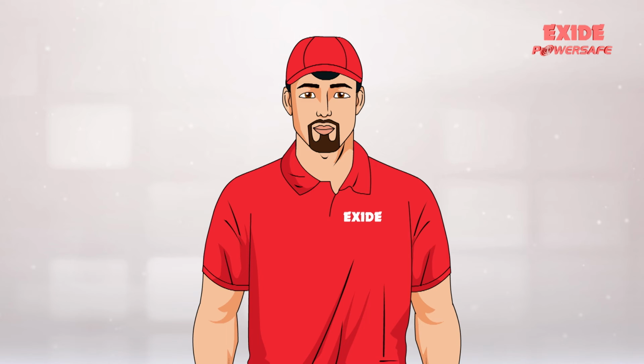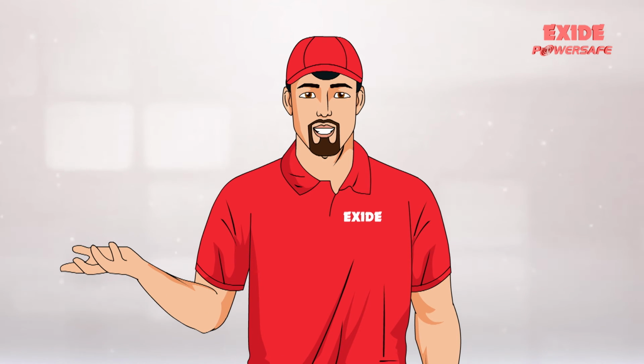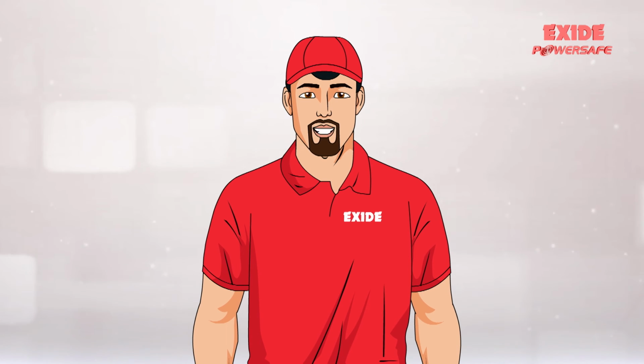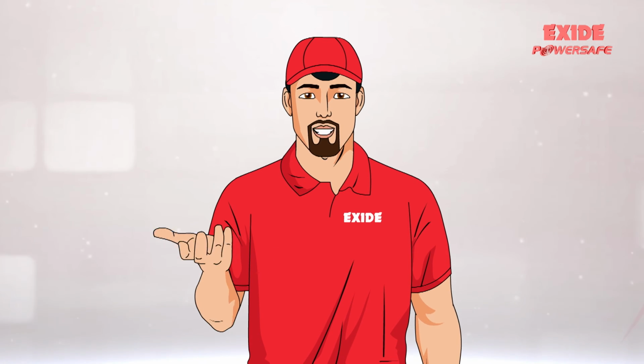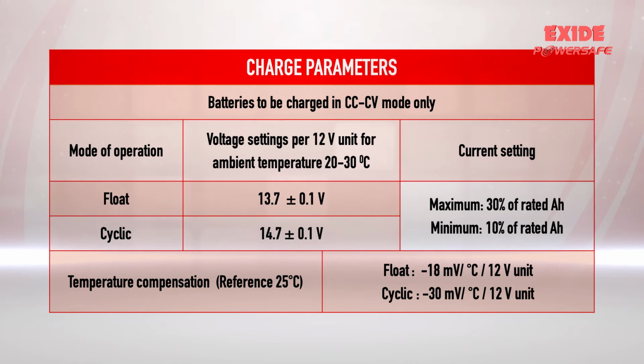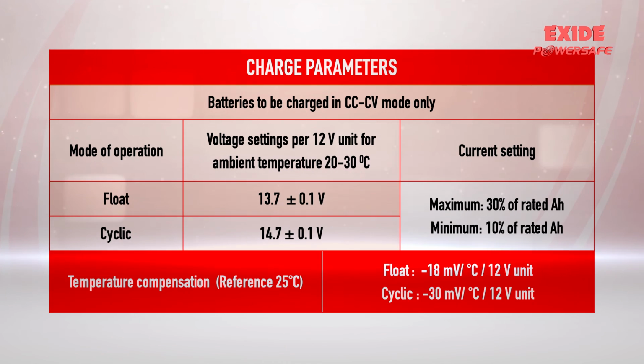Once installed and commissioned, the charging and smooth operation of your VRLA batteries can be done by the following checklist of activities. Correct charging of a VRLA battery is essential in optimizing battery performance and life. Constant potential charges with current limit facility only is recommended for normal continuous operation. This shows the charge voltage and limit current. The charging voltage of the battery must be reduced with increasing temperature and vice versa.